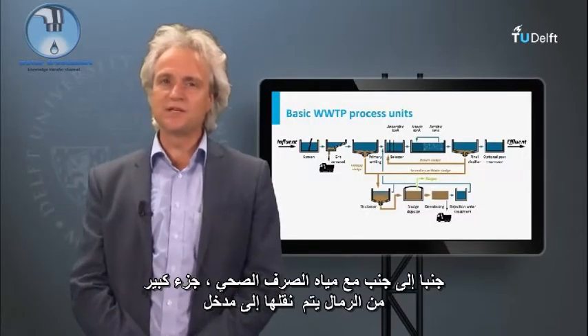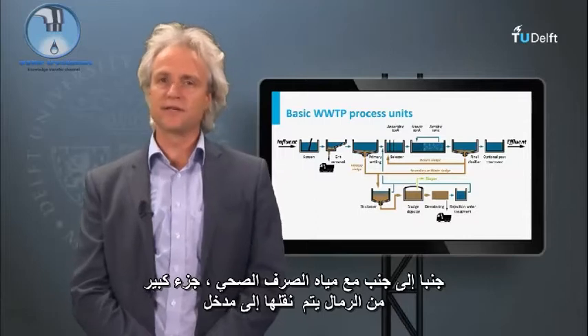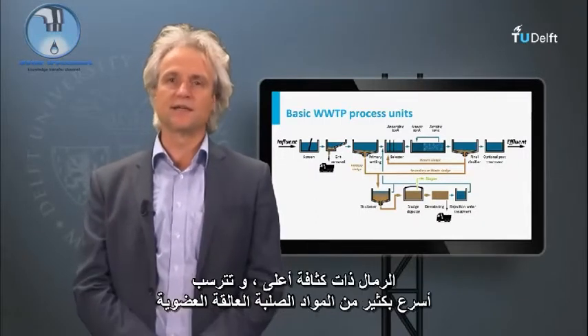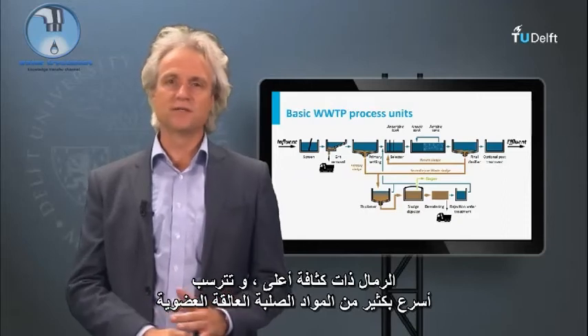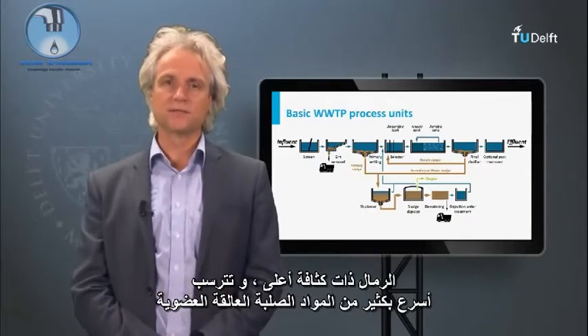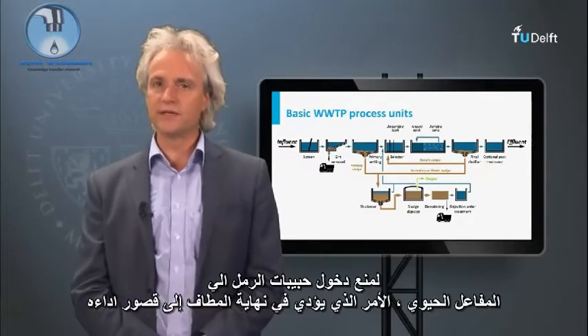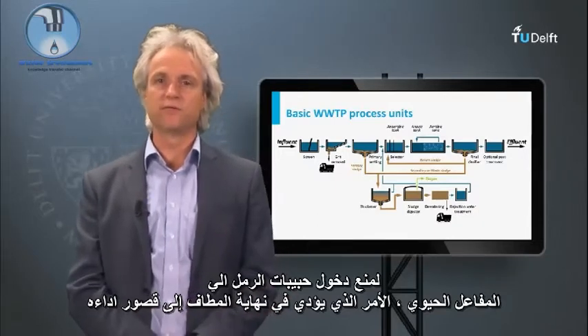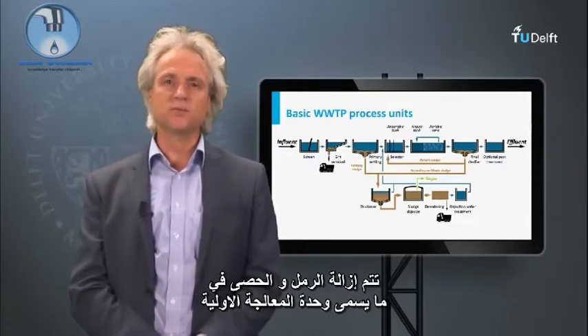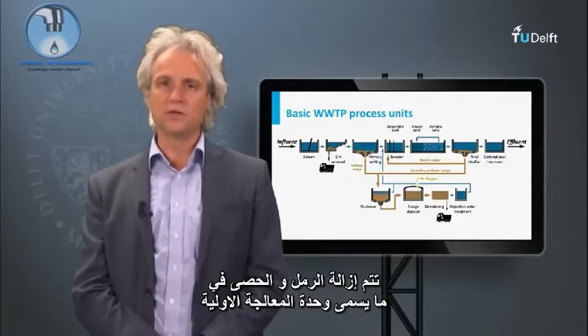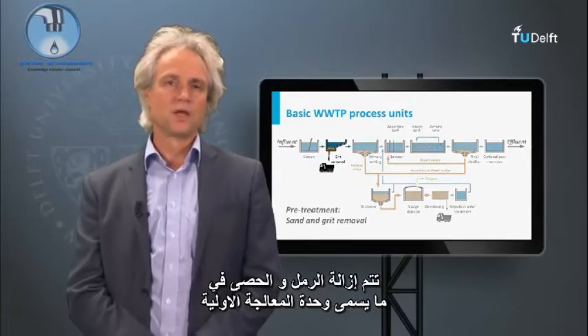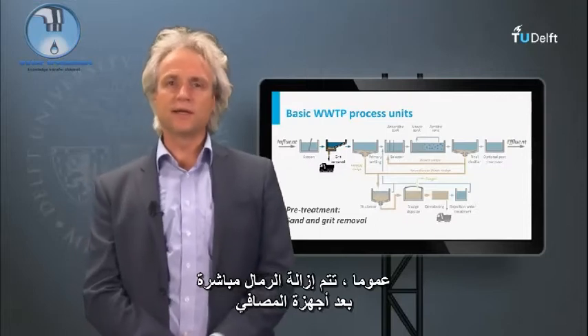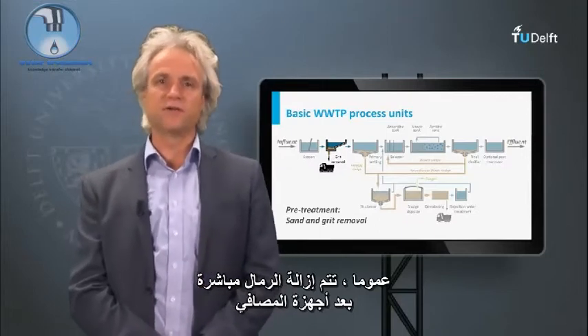Together with the sewage, a substantial fraction of sand is transported to the entrance of a sewage treatment plant. Sand has a higher density and settles much faster than the organic suspended solids. To prevent sand particles from entering the bioreactor and causing malfunctioning, sand and grit is removed in the so-called pre-treatment units. Generally, sand removal is directly positioned after the screening devices.